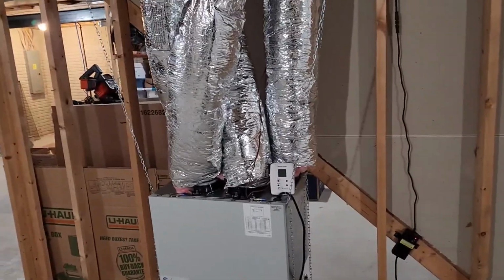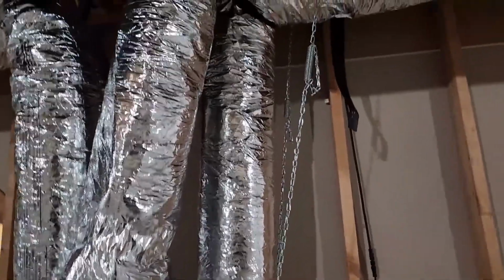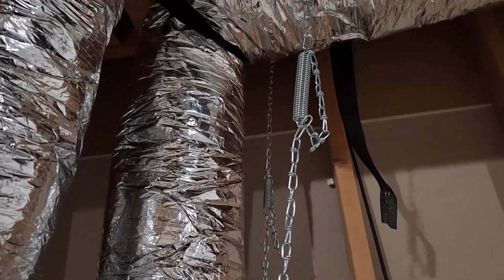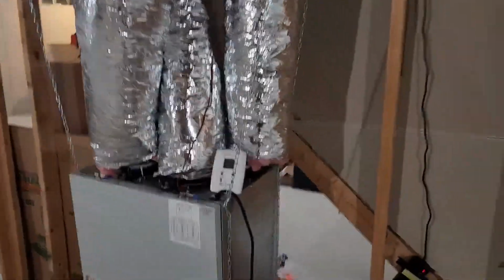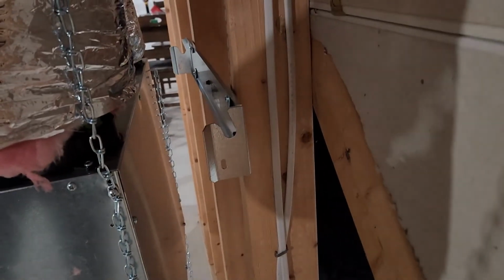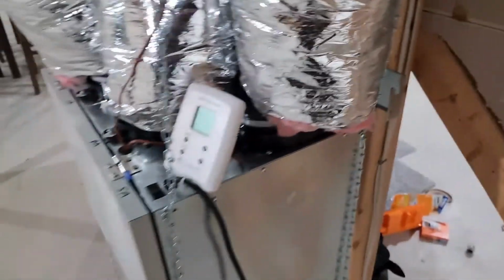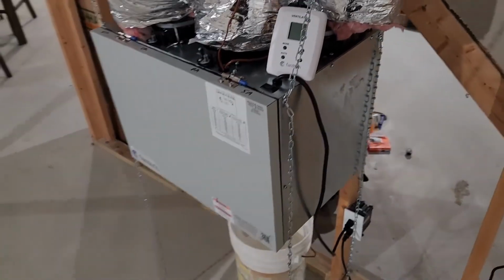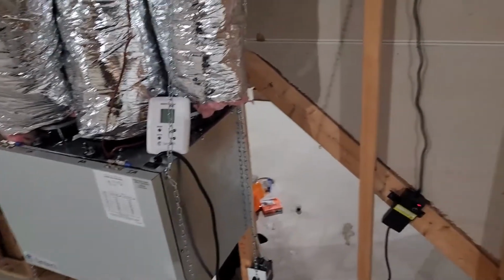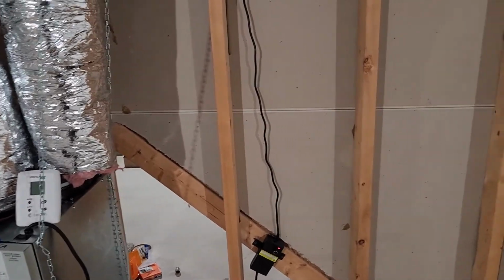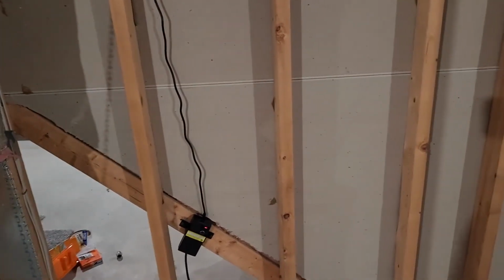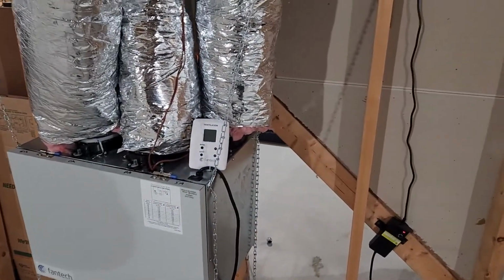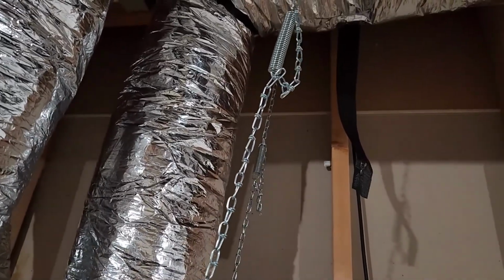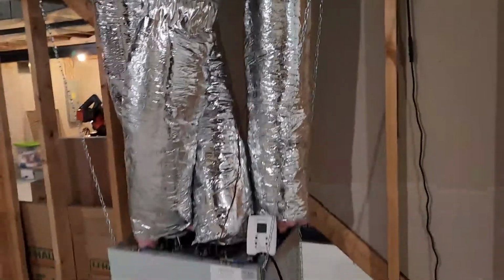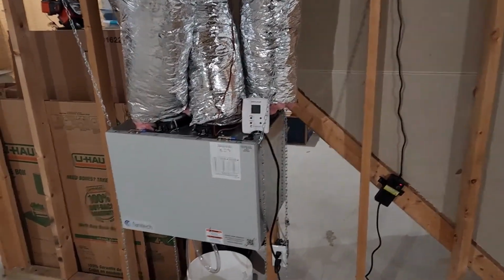I've got it mounted here on chains, and on each one of the chains I looped a screen door spring. So it's a poor man's anti-vibration install, because I first installed it to the wall using the supplied wall bracket. Because there are two fans in this bad boy, one on each side, your exhaust side and supply side, those fans, when mounted to the studs, were creating a low frequency noise. It sounded like a helicopter was going off in my stairwell and upstairs when this thing ran. So when it's installed with these four chains, you get really good vibration isolation, and you don't run into that issue as much, actually at all.